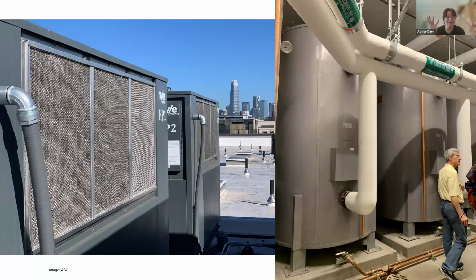These are just some photos showing an example of this type of design in San Francisco, and you can see, with that person for scale there, just how large these storage tanks can be sometimes. So you've got to figure out where the outdoor units are going to be located and where the indoor storage tanks are going to be located. Something to think about with tanks of that size is, can you get them through the door if one needs to be removed and replaced? So designing the space and the plant to allow for easy maintenance is a good idea. Next slide.